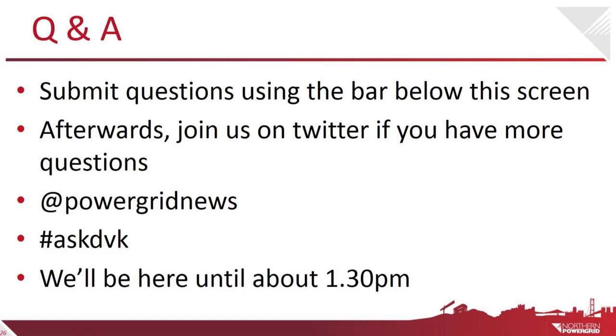Someone else has asked, does this take into account IDNO connections? An IDNO connection is where a private network operator has taken a connection from our network and distributes power to their own customers beyond us, running a private network that connects to ours. The answer is yes, because that IDNO is obliged to have an agreement with us for any contracted generation they want to connect into their network. We don't see all their individual generators, but we see an overall position at the interface between us and the IDNO network, through a contracted agreement. They're not allowed to connect additional generation onto a site until they've agreed with us that it's okay and doesn't affect our network, and if necessary, we've agreed with National Grid that it doesn't affect the transmission network. So that's covered off.